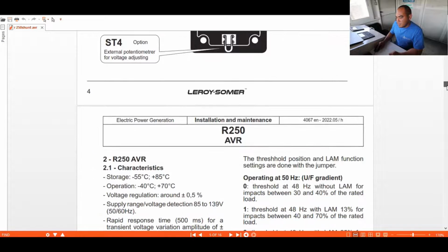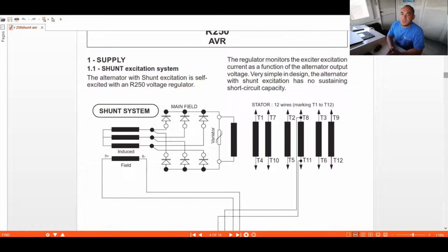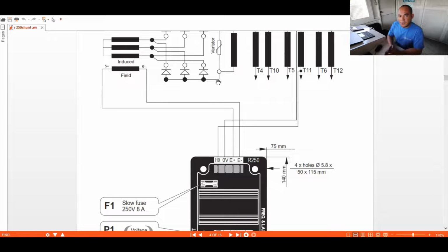But don't worry, this AVR or these connections have no sustained short circuit capacity, so you are safe from short circuit. If you have a short circuit in your load, there is nothing to worry about, because this one shuts down by itself. It cannot produce more voltage during the short circuit. Okay, so let me clarify, this is a shunt excitation system, which is the self excitation system. So this excitation system has no short circuit capability or capacity.